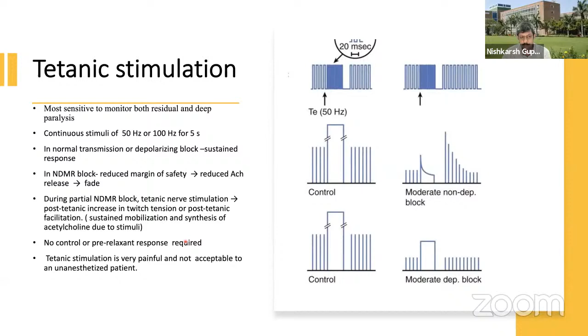So in normal transmission or depolarizing block, a sustained response will be there with tetanic stimulation. However, when a non-depolarizing muscle relaxant is given, the acetylcholine effect is reduced because of the blockade of the receptor, and so we will see a fade. During a partial non-depolarizing block, tetanic stimulation may lead to a post-tetanic increase in twitch tension, or post-tetanic facilitation, which we have discussed, because of accumulation of acetylcholine due to tetanic stimulation in the pre-receptor area. So no control or pre-relaxant response is required for tetanic stimulation. However, it is a very painful stimulus and practically not acceptable for an unanesthetized patient. So please don't use it when the patient is not anesthetized.